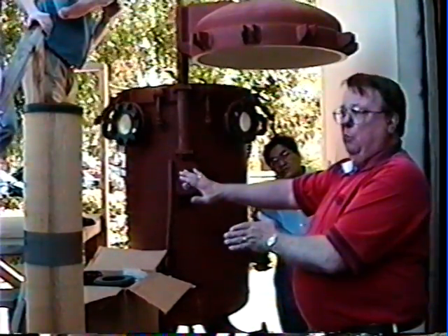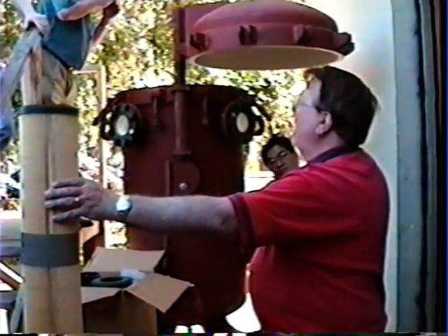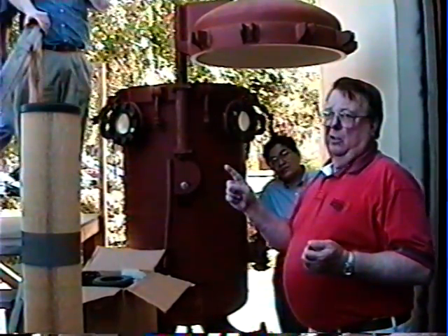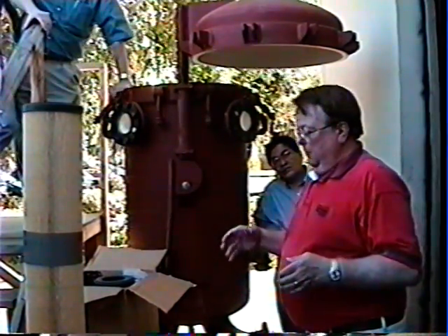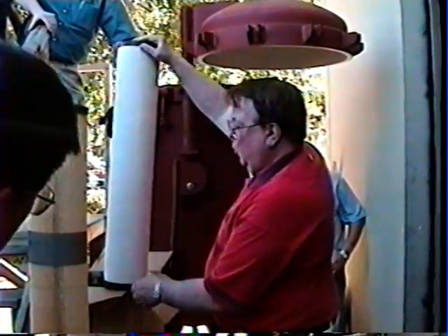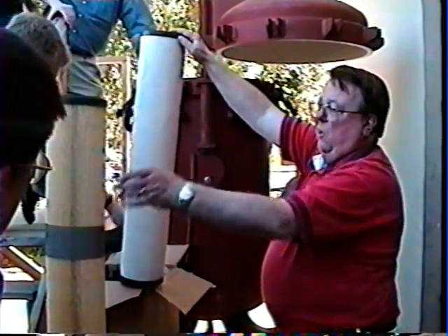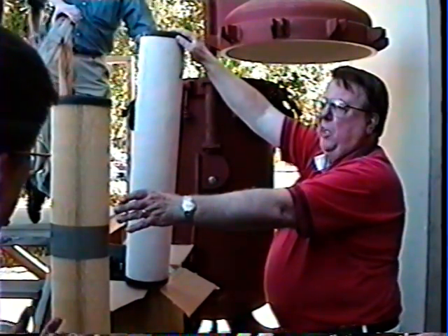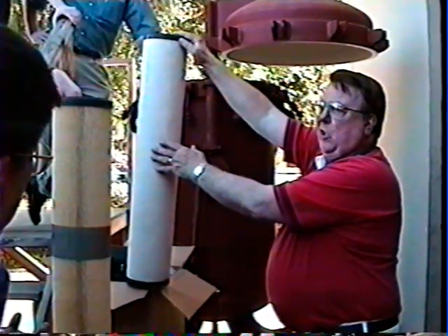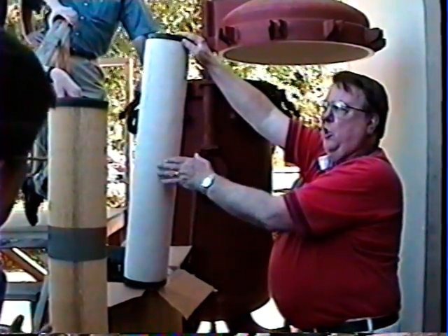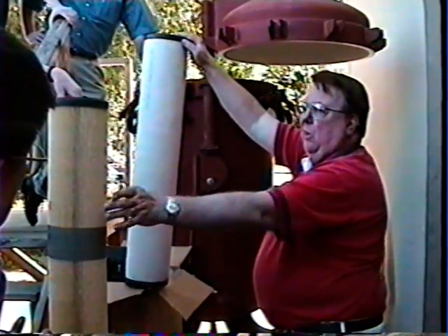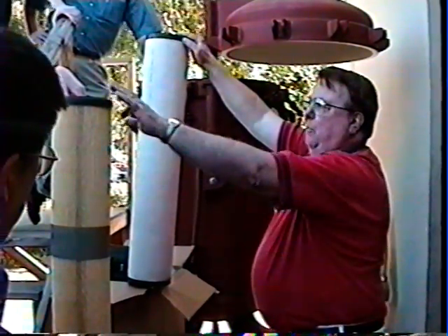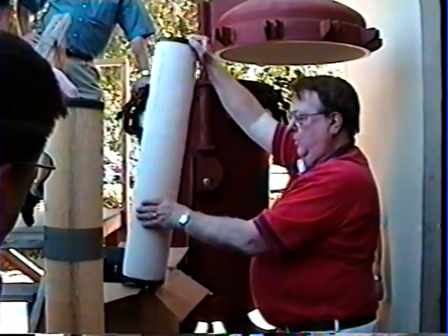As we get close to the airport, we're not going to use a 25 micron. We may have a 10 micron, a 5 micron, or a 1 micron because we want to clean the jet fuel up. And the big thing is we want to protect our coalescers. This may only cost the guy at the airport terminal $20. This may cost him $70 or $80. So what does he want to change out? 10 of these or 11 of these? Very easy to figure that math out. So this job is to protect the coalescers downstream.